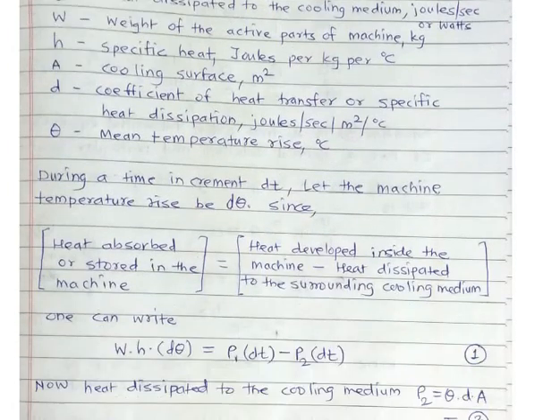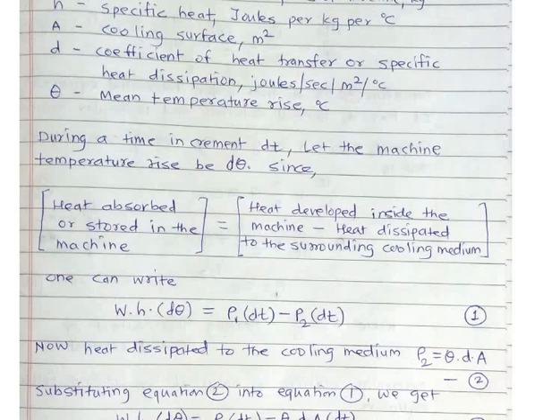During a time increment DT, let the machine temperature rise by D theta. That means when the time is changing by DT, temperature rises by D theta. Using the following heat balance equation — heat absorbed or stored in the machine equals heat developed inside the machine minus heat dissipated to the surrounding cooling medium — we can write expression number one: W into H into D theta equals P1 DT minus P2 DT.